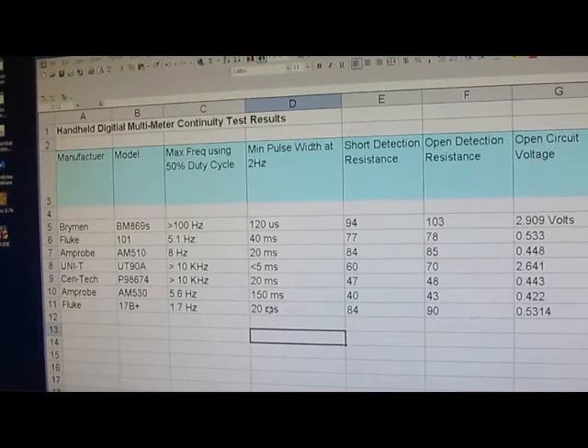So while the pulse width going into the Fluke can be quite a bit shorter than the Amprobe, the top end frequency is very low. So for my own application, I'd actually be better off with this Amprobe. I'd rather have the higher frequency. Actually, like this 510 here at 8 Hertz, that's almost perfect for what I would be using it for. And that'll also detect a 20 millisecond pulse width.